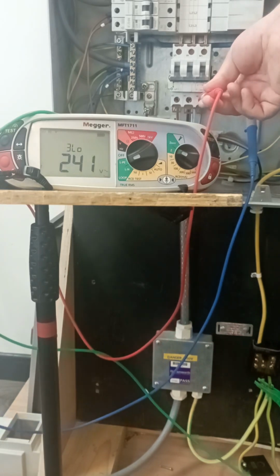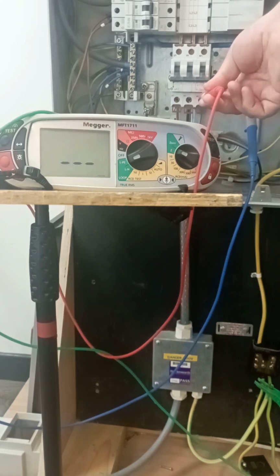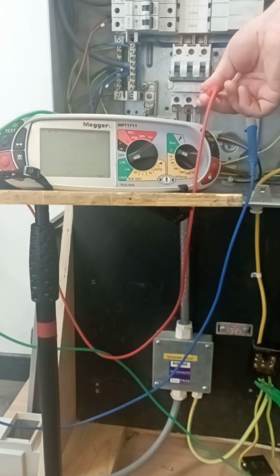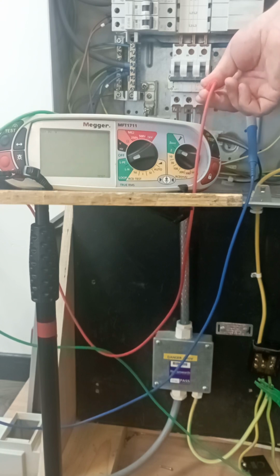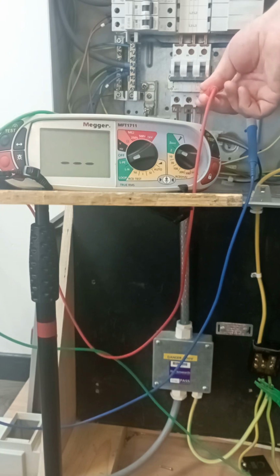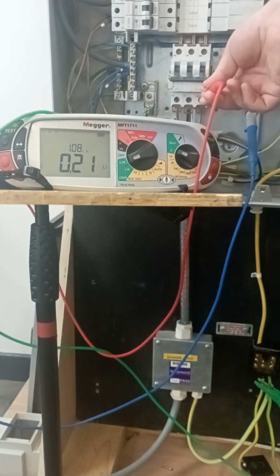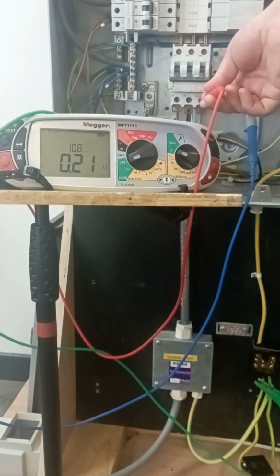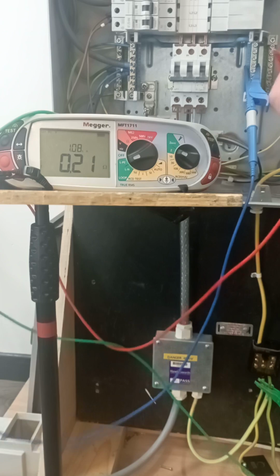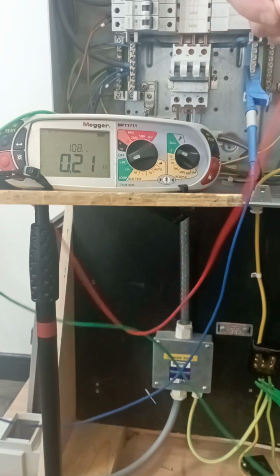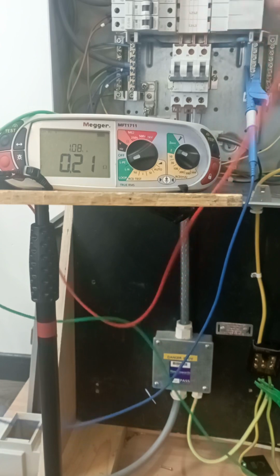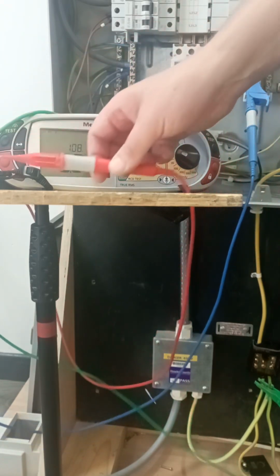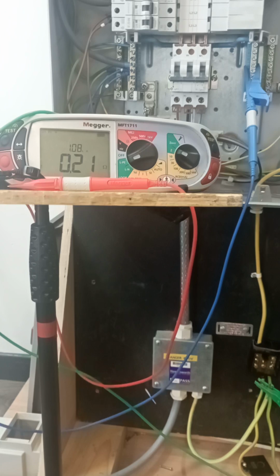Obviously this test takes quite a bit of time when it's on a low current setting. The one test I would say never to use is a 2-lead low current test. A 2-lead low current test takes forever and the accuracy of the readings is a mile out. If I didn't have this RCD upstream, I would probably be getting far lower earth fault loop impedance values than I have here. So line 3 I've got 0.21. So take those 6 values and I would pop them into a wee table and identify the highest of those values, and I would record that as my ZE for the installation. Okay. Now at this point, this earthing conductor down here is getting reconnected straight away.